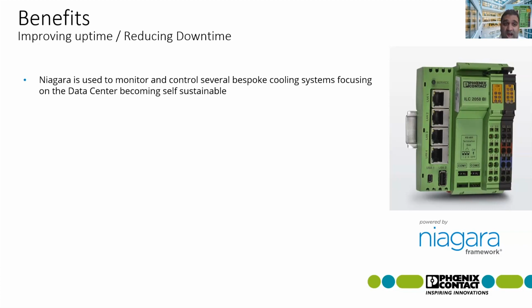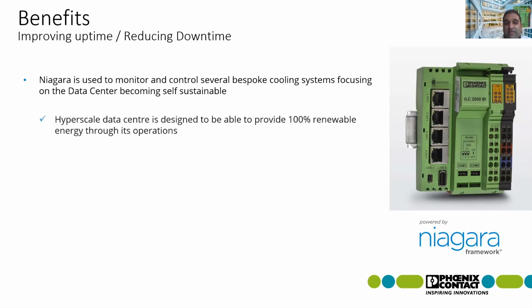Niagara was used to monitor and control the bespoke cooling systems. Earlier I mentioned using rainwater—that's exactly what the customer does. It collects rainwater and puts it through air coolers, mixing the two to bring the temperature down within the cooling, within the data center. So it's about becoming more sustainable, which was quite a focusing point for this data center customer.